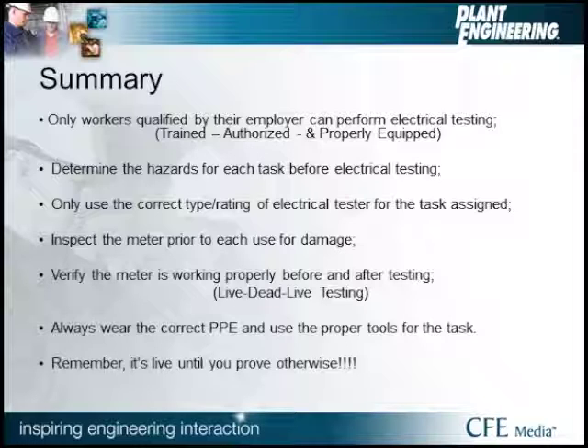Oh, that's fair enough. Let me summarize very quickly. Only qualified workers, workers who have been approved by their employer, can perform any type of electrical testing. Before any testing is done, a complete hazard analysis needs to be performed. We're looking for shock hazards, arc hazards, or any other hazards that may be present in the workplace. We can only use the correct type or rating of electrical tester for the task assigned. And again, I want to make sure we understand that the rating on our meters is not the same as the category rating for clothing.